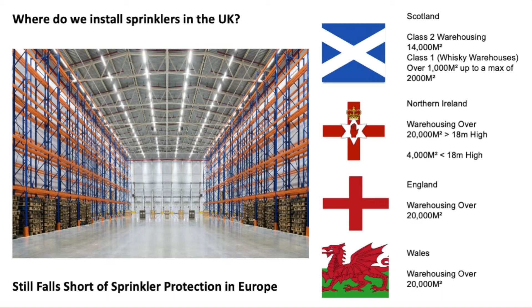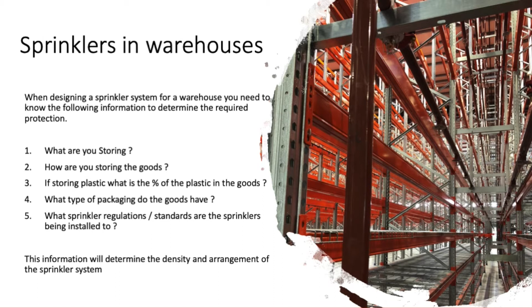So we're going to the design part of it. When you're designing a sprinkler system in a warehouse, you need to know the following: what you're storing, how you're storing it, if you're storing plastic, what percentage of plastic is in the goods, what type of packaging the goods have, and what sprinkler regulations or standards you're going to be installing to. This information will determine the density and arrangement of the sprinkler system.